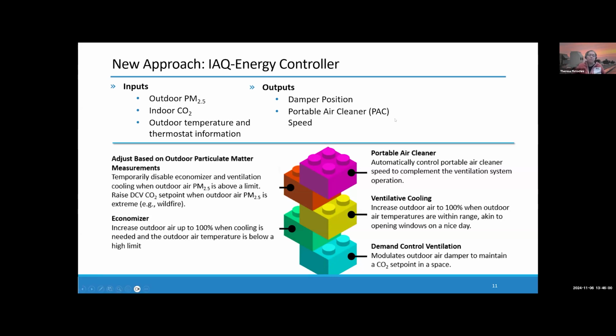And so the way that this works is it starts with a demand control ventilation algorithm that maintains a CO2 set point. It adds an economizer. It also adds ventilative cooling. So meaning when outdoor air quality is good and temperatures are within a certain range, we're going to ventilate 100%, which is kind of like opening all the windows. And we can actually get more outside air without impacting energy savings than we would otherwise.